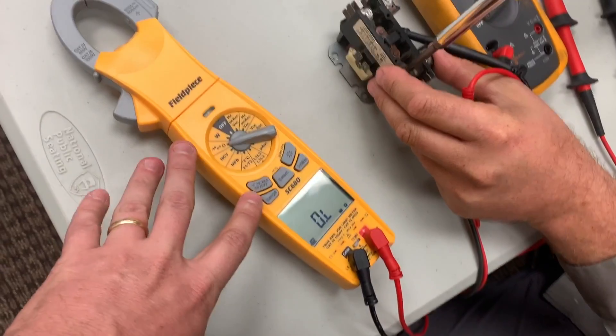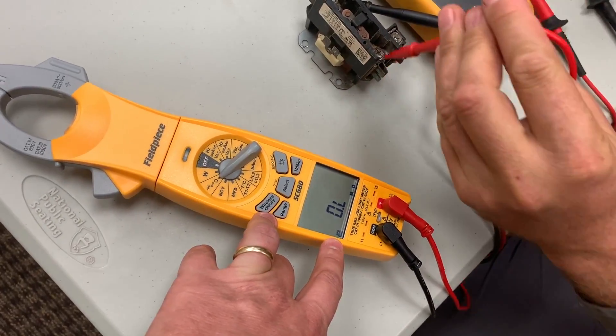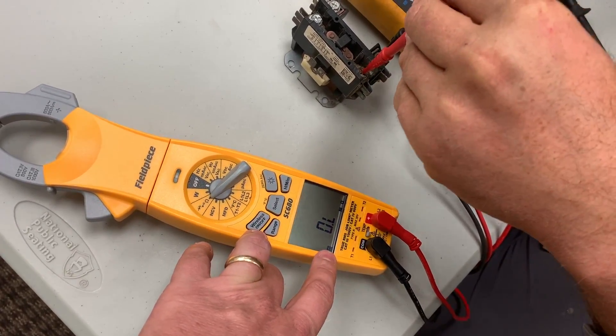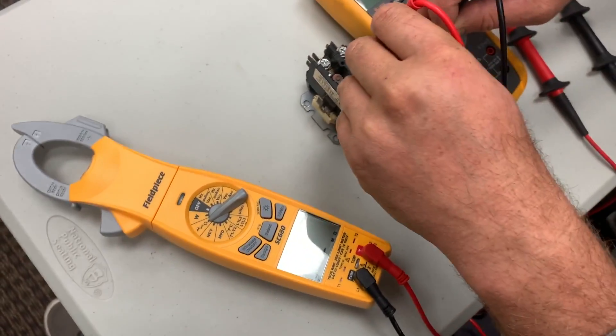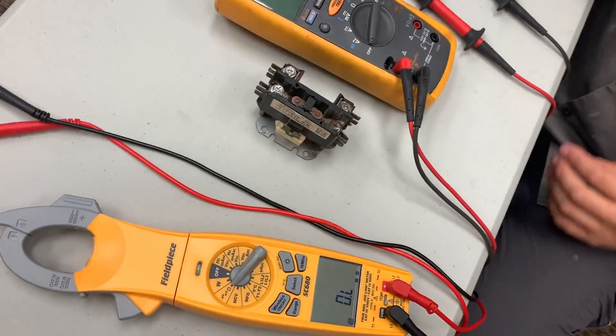The thing to consider here is when you're using a typical multimeter, it's using pretty low voltage to actually make the path. This is why in some cases you won't find a short circuit with a regular meter on a compressor, motors, or switchgear. Now we're going to use the Fluke 1587.